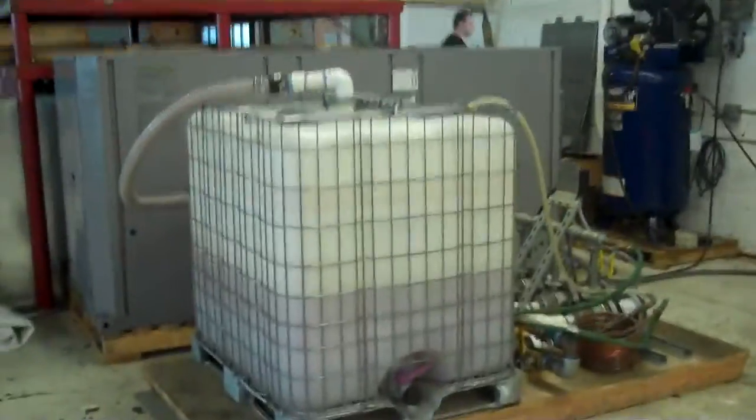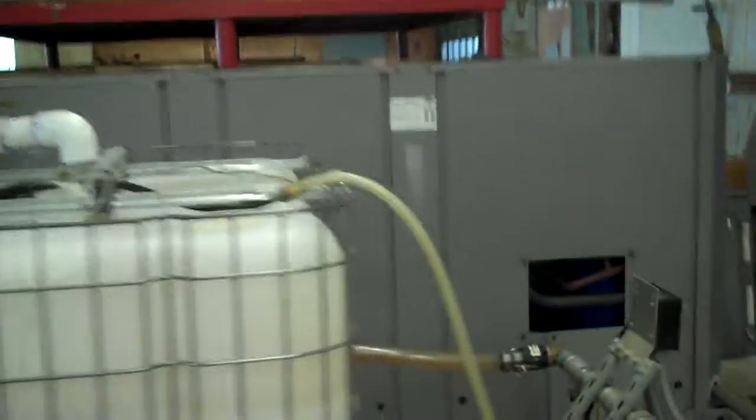This is our video number two for our 25 ton air-cooled chiller carrier aquasnap low temperature application. We put the primary side covers on which you need for proper air flow over the coils. The coils are on the back side here by the way.